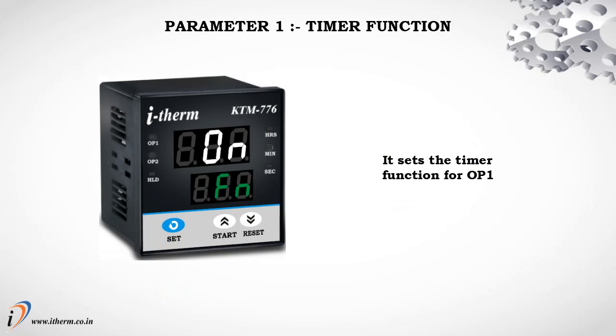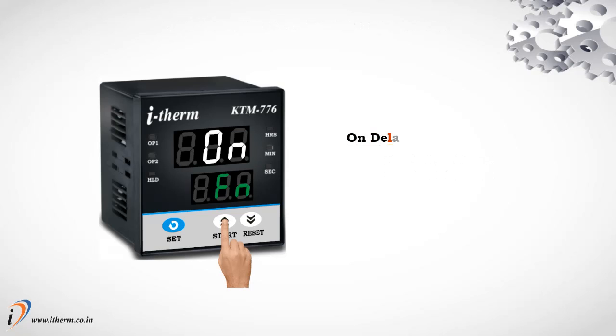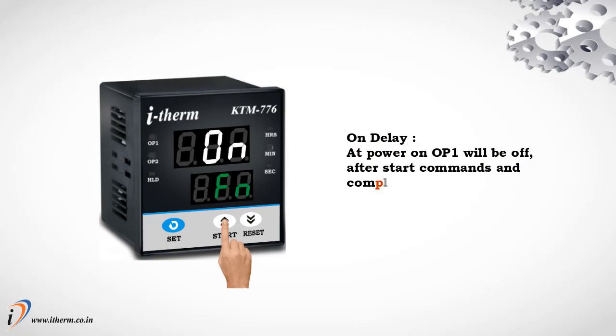Parameter 1: Timer Function. It sets the timer function for Output 1. On Delay: at power on, Output 1 will be off. After start command and completion of the time delay, Output 1 will turn on.